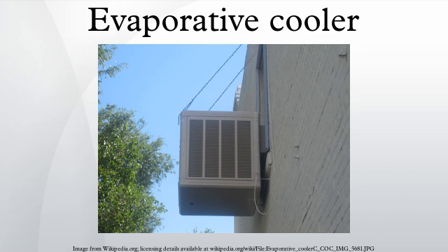Once the wet bulb temperature and the dry bulb temperature are identified, the cooling performance or leaving air temperature of the cooler may be determined. TLA = TDB − E(TDB − TWB), where TLA equals leaving air temp, TDB equals dry bulb temp, TWB equals wet bulb temp, and E equals efficiency of the evaporative media. Evaporative media efficiency usually runs between 80% and 90%, and the evaporation efficiency drops very little over time.